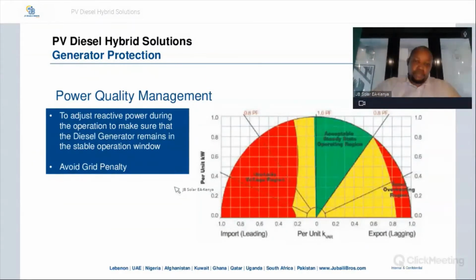Next is power quality management. This is to adjust the reactive power during operations and make sure that your DG is operating in the stable window. Here in Kenya, we have power quality of between 0.8 and 1. And if you go below that power factor, you get penalties from the utility company. So to make sure that you're operating within the set limits, the hybrid controller will be able to adjust the power quality so that you're operating within the optimal level.